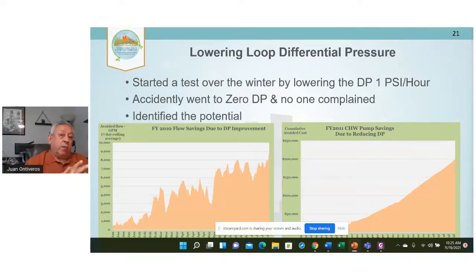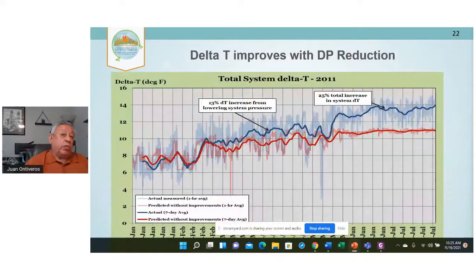Now, remember what I mentioned: if you have too high a pressure, the control valves in the buildings do not work. So the building gets too cold, and you end up dumping that cold water back into your return water temperature pipe, so you have a lower delta T. If you lower the pressure, you don't get too cold, and you don't dump that cold water into the return water temperature.